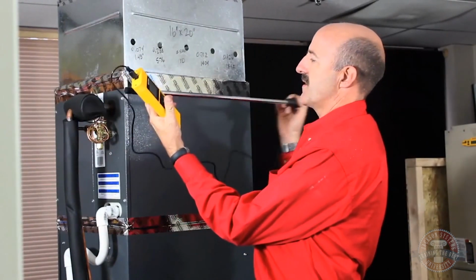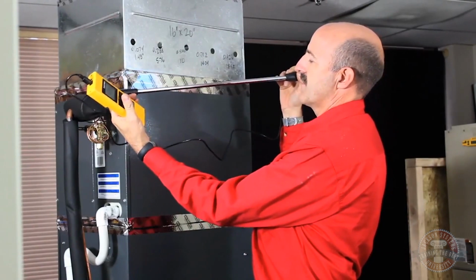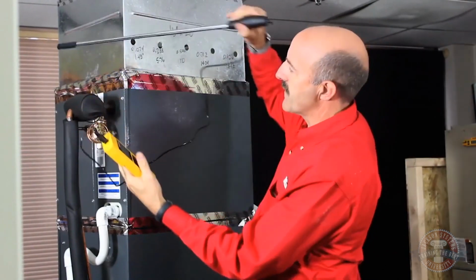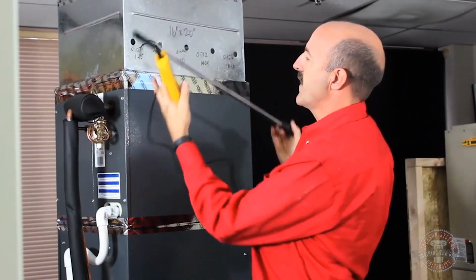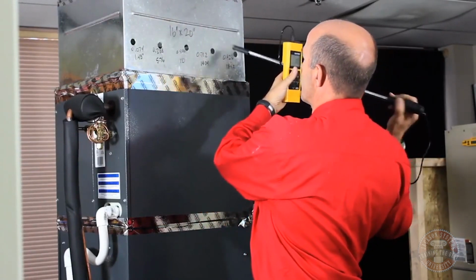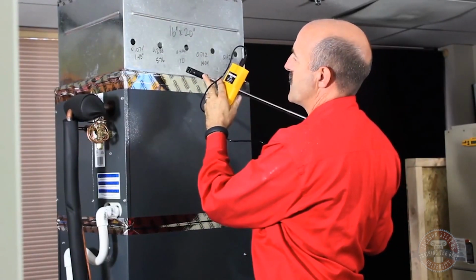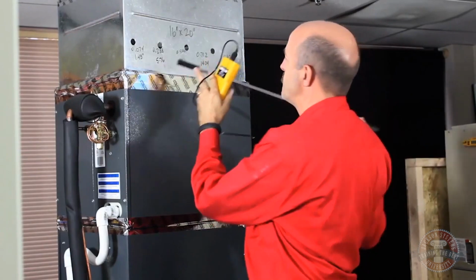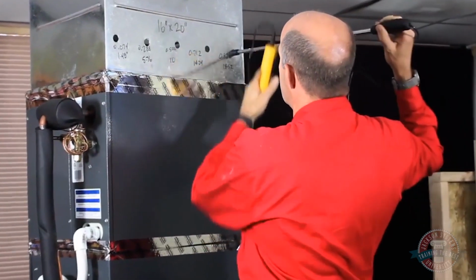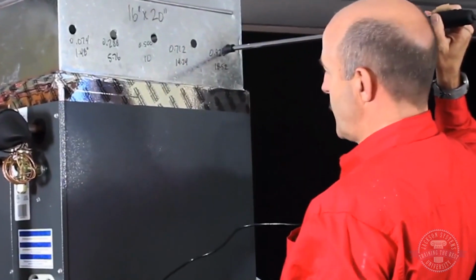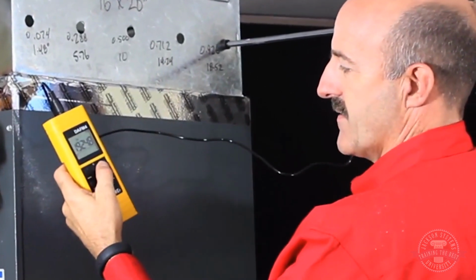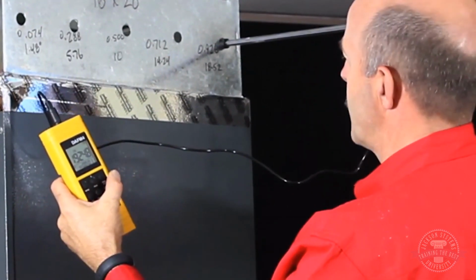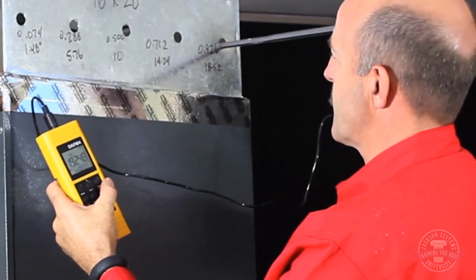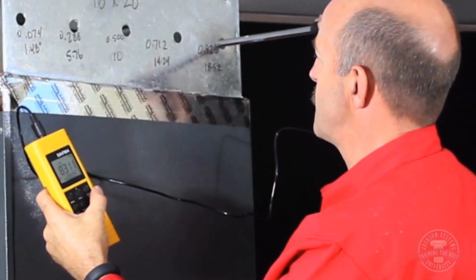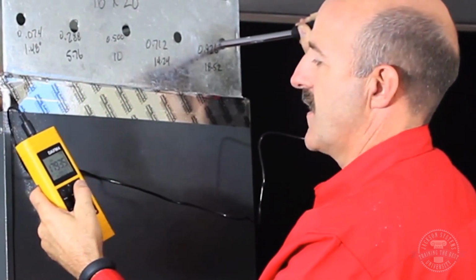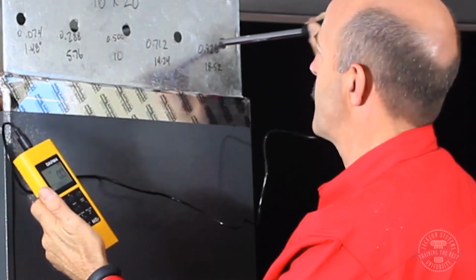So first you make sure that the vane is extended long enough to cover the depth. And then you check there's an arrow on one side, that's the direction of the airflow. And I'll put that right on the inside of the ductwork, and then I hit start and slowly traverse that access hole until I reach the other side, and then I hit stop.